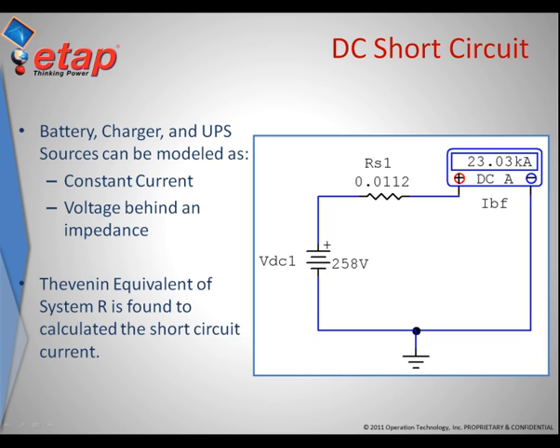First, let's start by talking about DC short circuit. Before we can perform any DC arc flash analysis, we must first describe the impedance and the voltage or current source in our system. In this case, we are referring to battery banks, chargers, UPS, and rectifier sources.